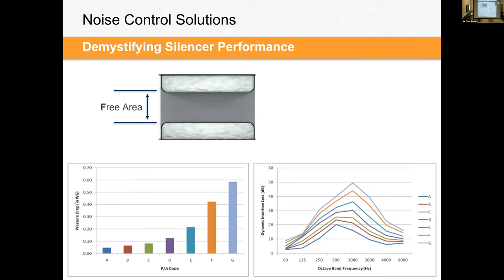If you look at these letter codes and these colors, this graphical comparison sort of shows you what's happening. On the right side, this is our insertion loss. So 63 to 8,000 hertz. Your insertion loss kind of has this bell curve to it, and that's quite common. Usually low frequency and high frequency are kind of lowest, and then the mid octave bands have higher insertion loss. At the widest open free area, an A code or 57.5 has the lowest insertion loss because of that wide gap, small baffles, low insertion loss. The pressure drop is also very low because you've got that wide gap, less obstruction, kind of less than a tenth of an inch of pressure drop.